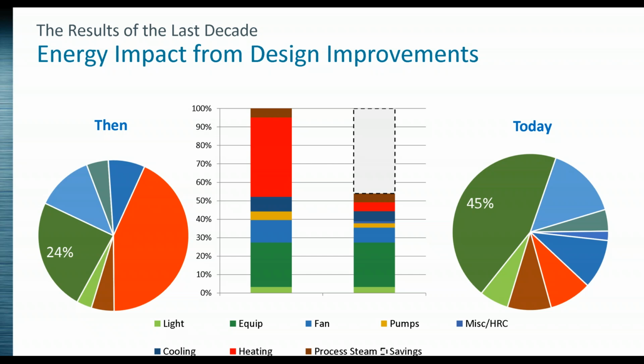In this case, this was taken from a large biology lab building - we see a lot of biomedical facilities with this sort of signature. When we looked at where we were from an equipment perspective, we were about 24% of the overall pie. But as the design team, we've wrung out a lot of the opportunity and savings, reducing heating dramatically with those strategies I talked through. We've reduced cooling, and in many cases fan energy and pumping have gone down because of that. But we've gotten to a point where there's not much more we can do until we begin to tackle the equipment - that equipment starts to represent almost 50% of what remains.